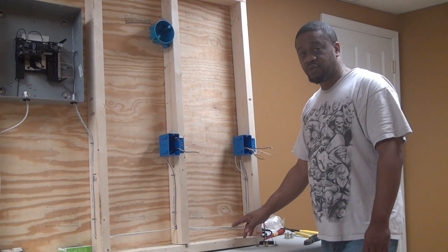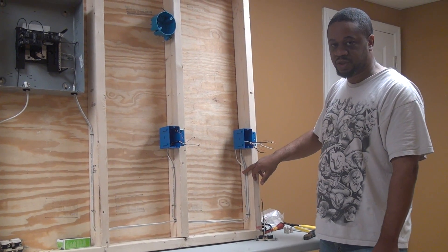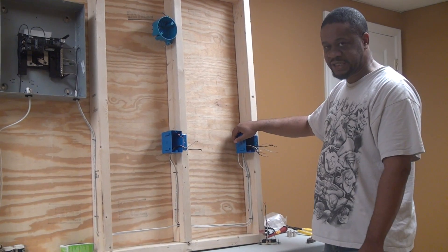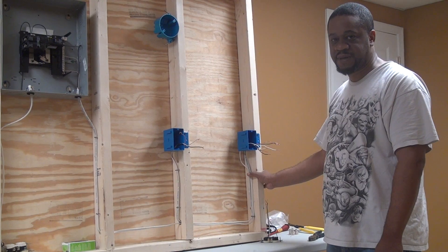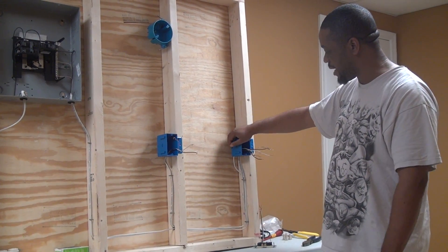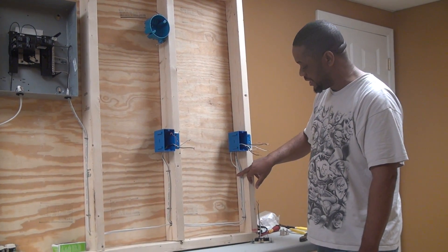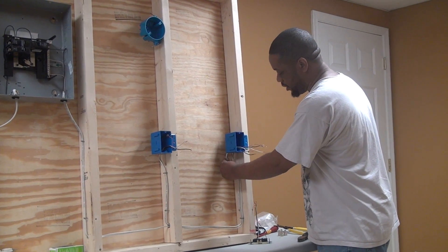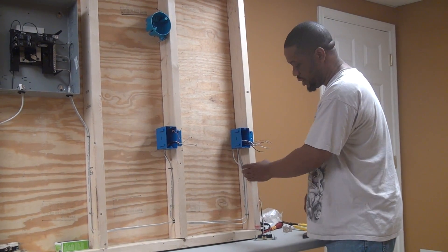When you're running your Romex cable, you want to put a strap every four feet. The code requires four and a half, but I'm going to tell you four. When you're using plastic boxes, you want to make sure that you have a Romex strap within eight inches of your box. The code says 12 inches, but for plastic boxes, you want to maintain a strap within eight inches of your box, mainly because you just have knockouts in there and there's nothing really holding it.